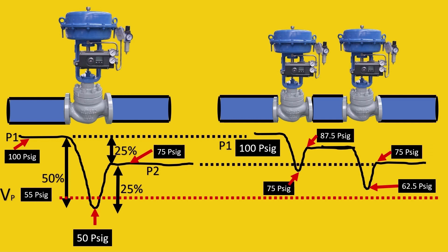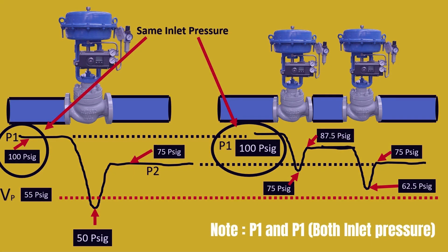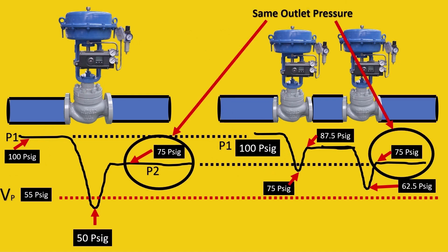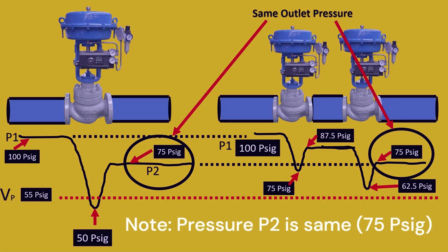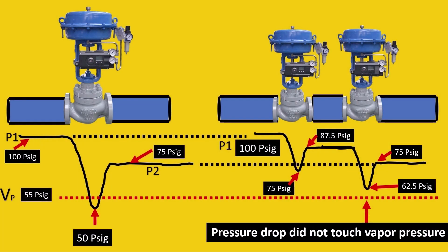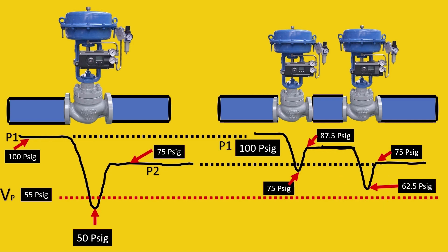The amazing thing starts here. If you notice, the P1 and the P2, the pressure at the inlet is the same, right? 100 psig, 100 psig. The pressure at the outlet is also the same: 75 psig and 75 psig. However, did you notice that the pressure curve in the second case did not touch the vapor pressure? So cavitation did not happen.